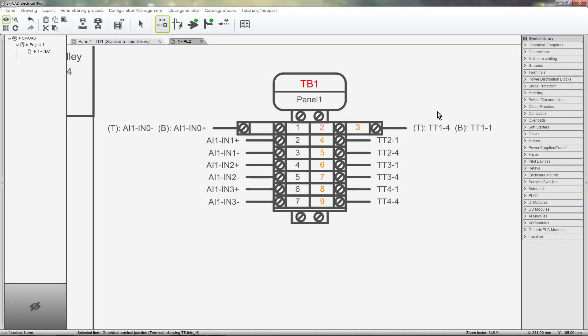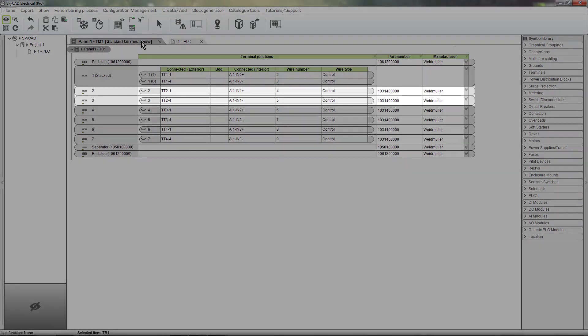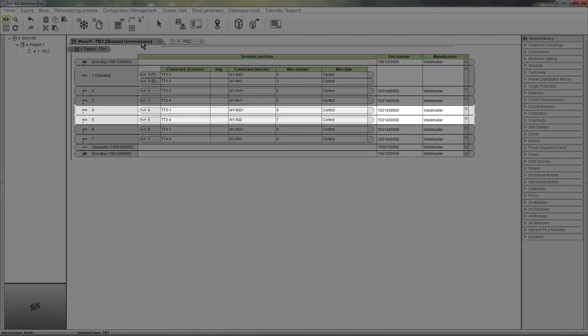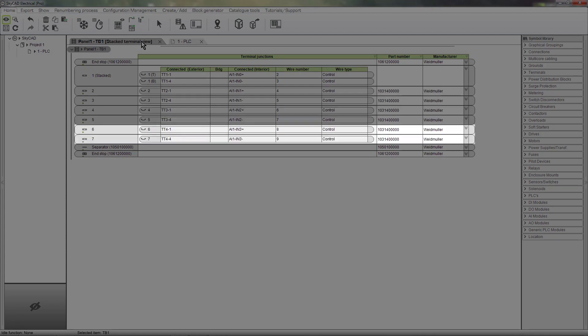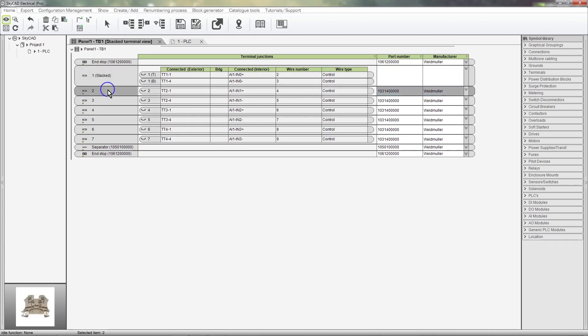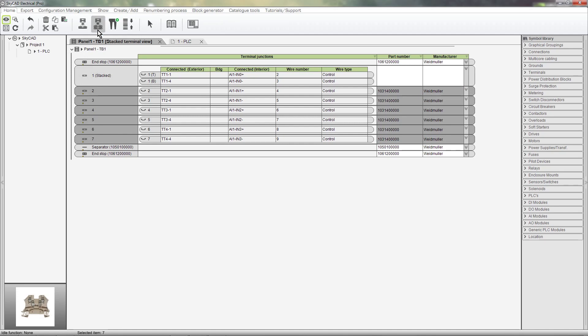We can also stack terminals in groups instead of one by one. This can be done from the Terminal List Views. Let's say I want terminals 2 and 3 to become a Stacked Terminal, 4 and 5 to become a Stacked Terminal, and 6 and 7 to become a Stacked Terminal. Select all the terminals you want stacked and select Group Stacked Terminals.